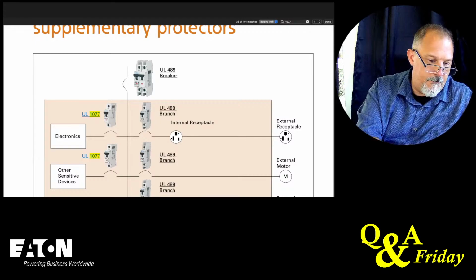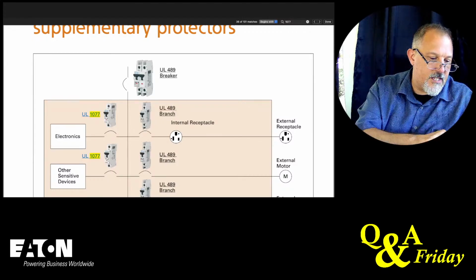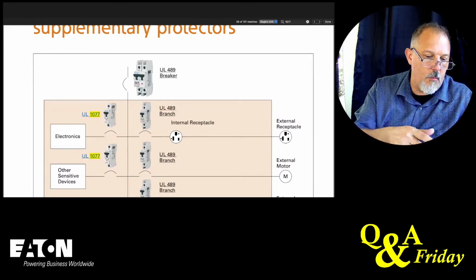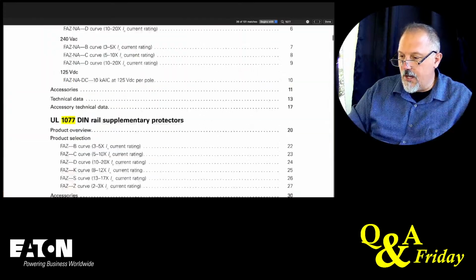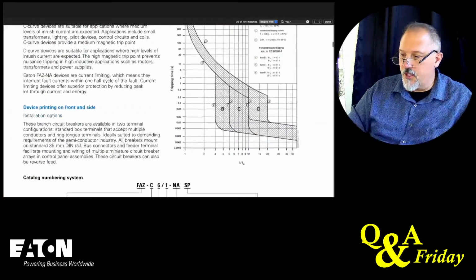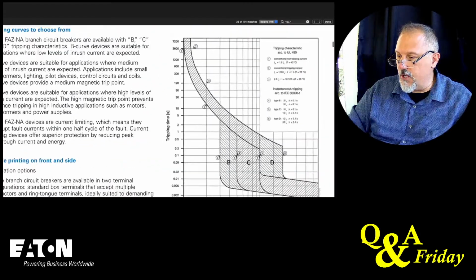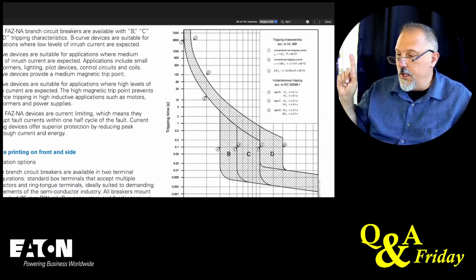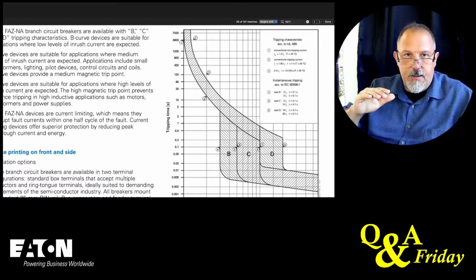When he says do 1077 devices have only thermal overload or both thermomagnetic? So he's really talking about the trip curve. This is what I would call the trip curve. It's the time current characteristic curve.